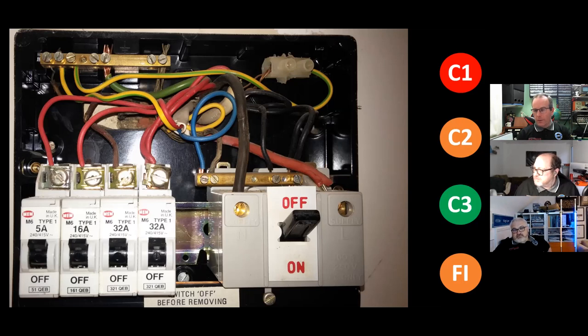This mess was supplied from another consumer unit. Oh, great. Daisy chaining. This was an old one, and then some person put a new one in the kitchen, which was also a total disaster. I think we're going to see some examples of that on our commercial industrial ones, where people run boards off of boards off of boards, then wonder why they don't get the necessary fault current values to trip any breakers. So we start with C2, but do we need to see anything else to go up to C1 here?